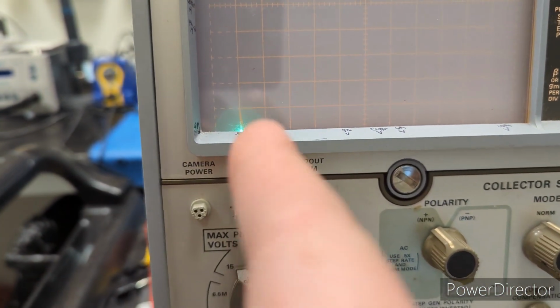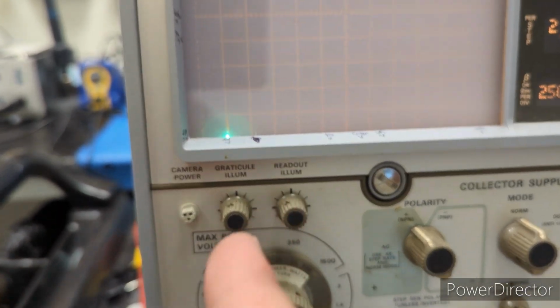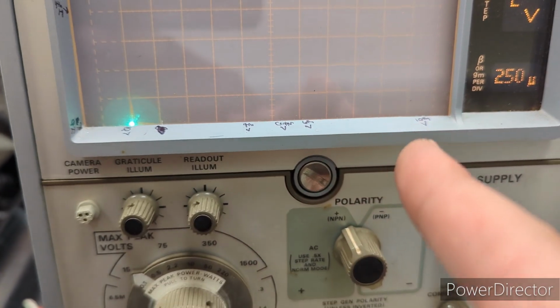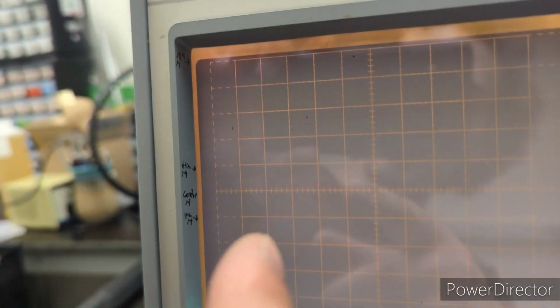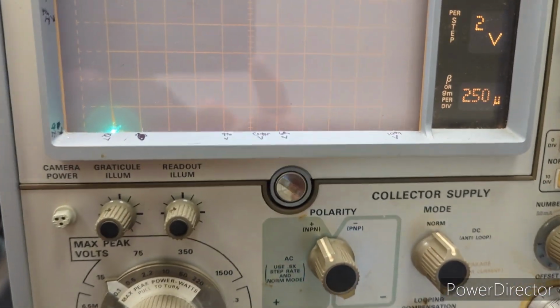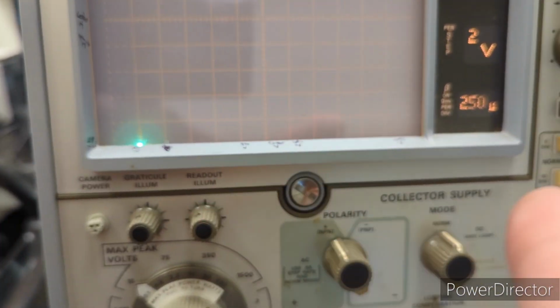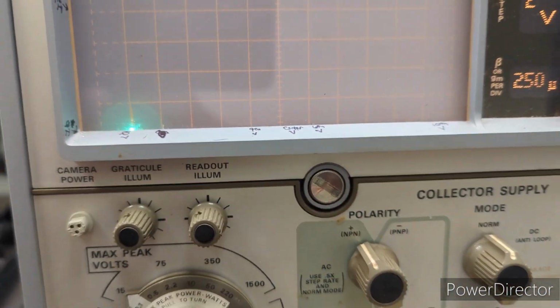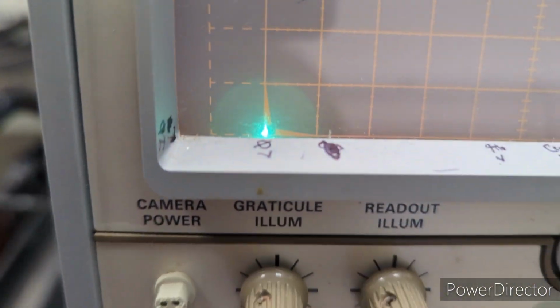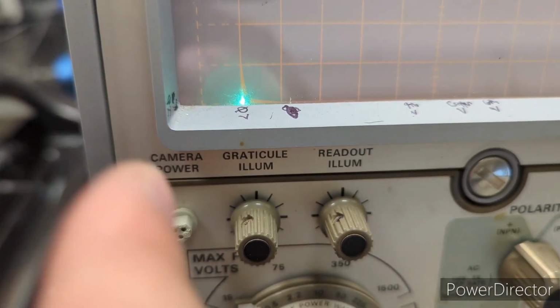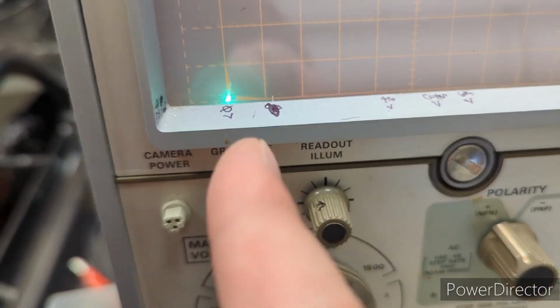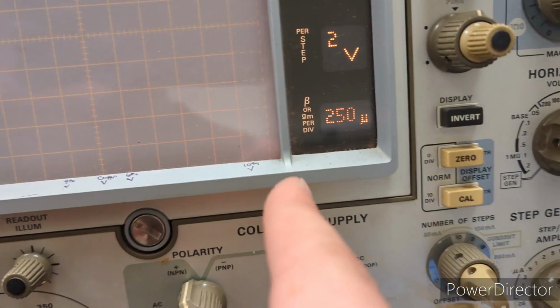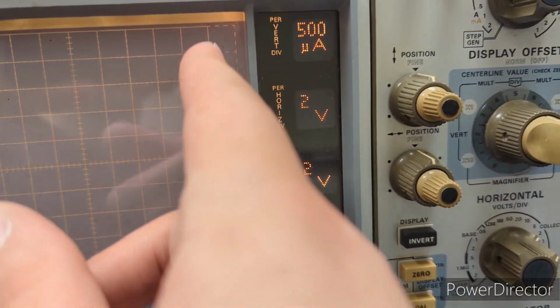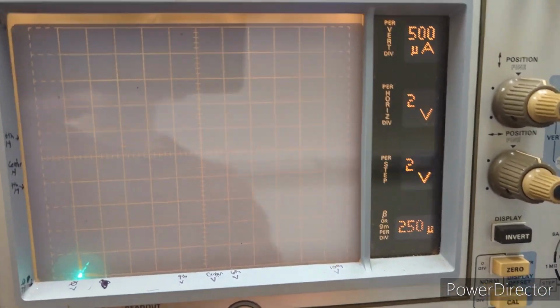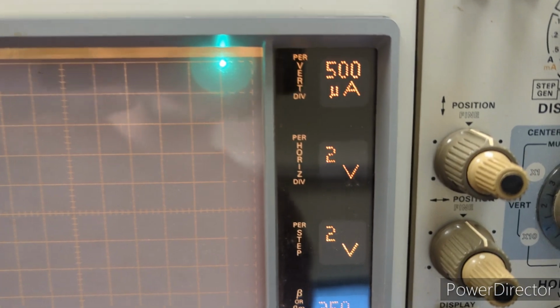setting. So this is where NPN should be at the 0, where both the vertical and horizontal 0 graticules meet. I was getting tired of flipping to the example graph in the service manual, because I kept forgetting the notations for each of the graticules, and so I just wrote them on the instrument until I can memorize them. But anyway, that's where the vertical and horizontal 0 graticules meet, right down there for NPN, and then PNP should be where the 10th vertical and horizontal graticules meet, which is right in that corner there. And so you can see, switching to PNP, we are there.